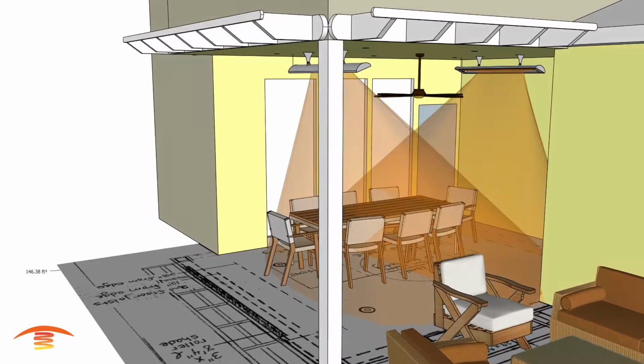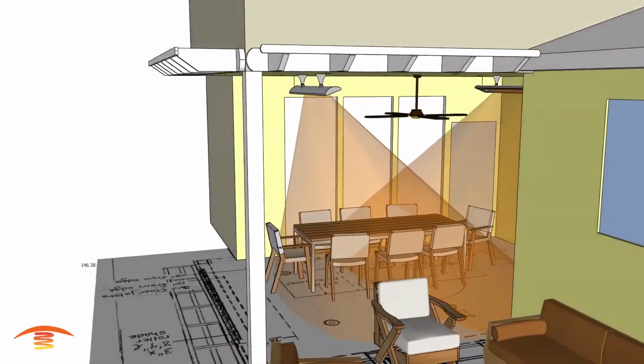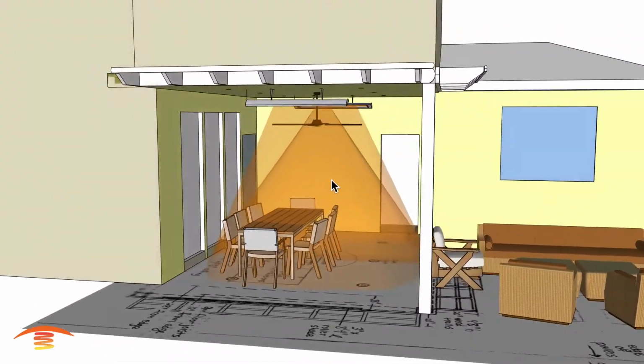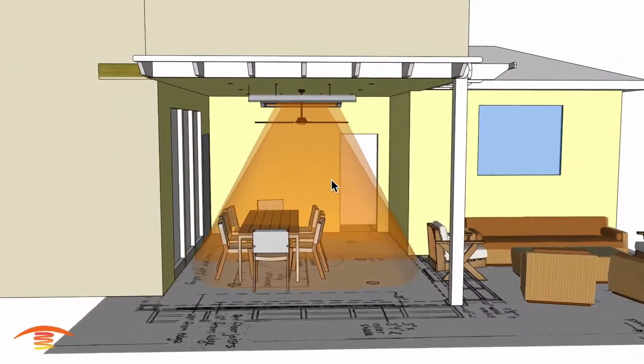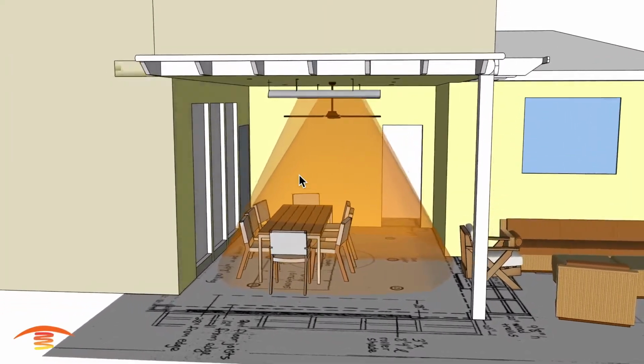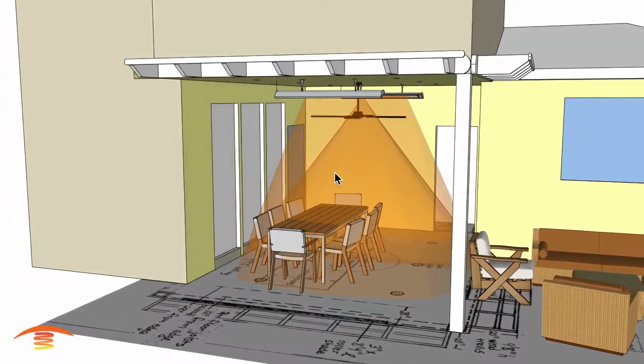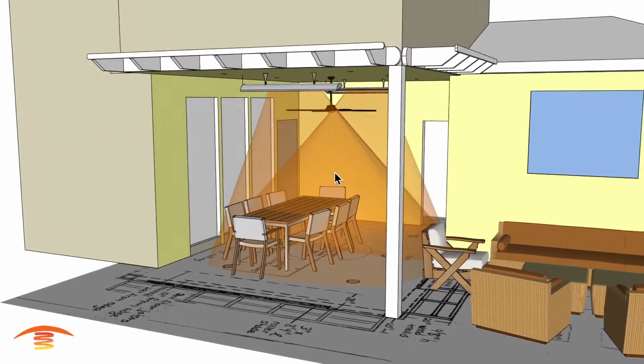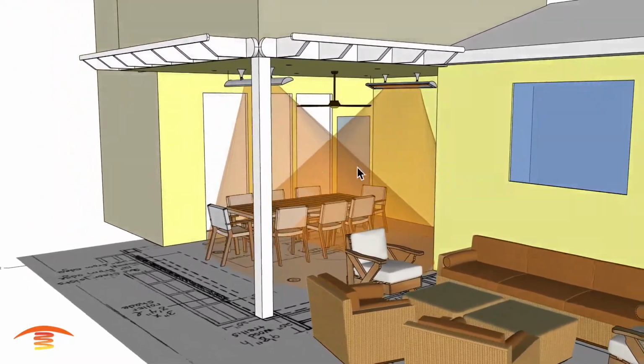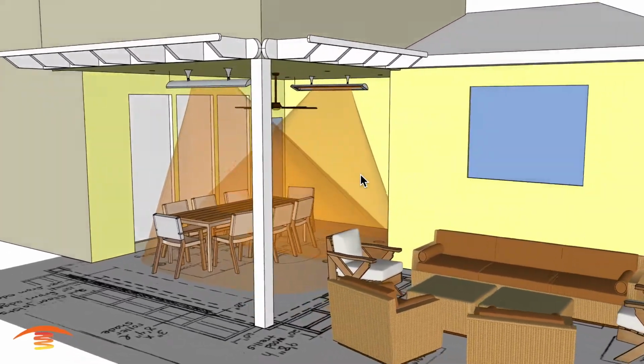And let's go ahead and turn off those clearances, and we'll look at what a CD would look like in the same position. So that would be what a CD would look like, and I think that would be much more ample power. I would consider the CD 6024s more than the Slimline just because of the output. I just don't encourage placing equipment out there where it isn't really producing what you're looking for. So that's why I like the CD 6024 in this kind of application better, because of the climate.